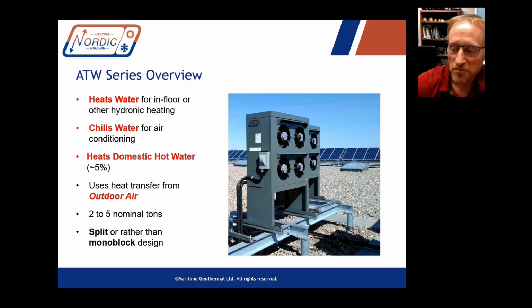Maybe not. Might not be a part of this presentation, but in the manuals we have for both series, or for all of our series, we have lots of piping diagrams with simultaneous heating and cooling and this sort of thing. Certainly in the ATW manual, which I'll show you where to find, there are diagrams for the 2 buffer tanks and a single buffer tank. Also, like putting a boiler in parallel with the heat pump. So it's good to have these recommended diagrams, because if you follow these diagrams, you know it's going to work. And there's lots of other ways to do it, but then if it doesn't work, you're kind of on your own there. So yeah, lots of different ways to do things for sure.